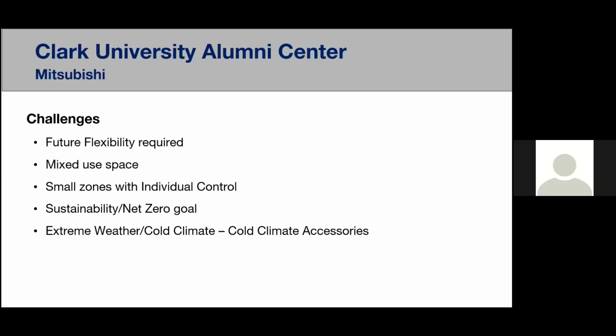And then lastly, extreme weather, cold climate. I mentioned it was around 0 degrees. So we did need to use a low ambient heating condenser, which was rated down to negative 13 degrees to produce cooling and heating capacity down to negative 25.